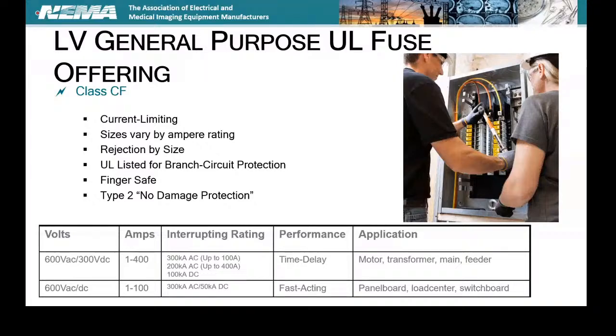You know how we got 300,000 amp interrupting? We had to update the entire lab just to feed the fuse current, because these things are so efficient that it's just a matter of how much current you can deliver to it. But we don't have any equipment that we can rate 300,000 amps. Finger safe solution, again, Type 2, no damage protection.